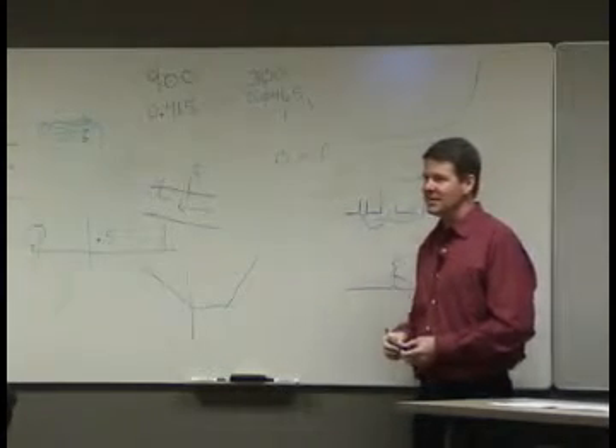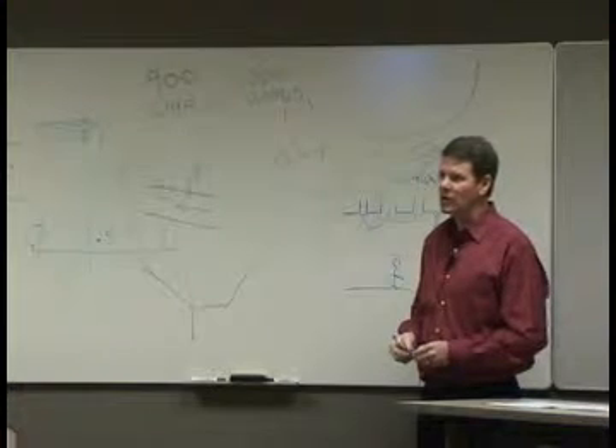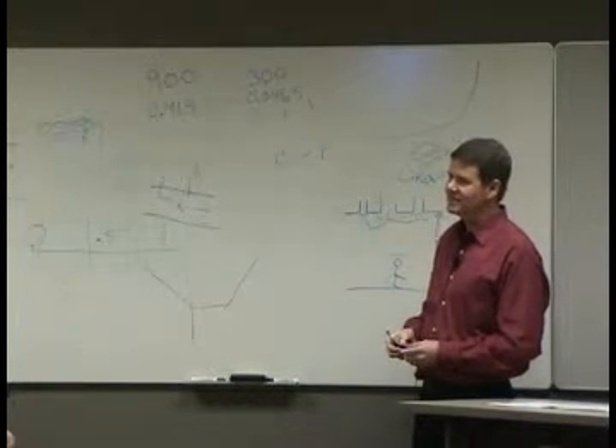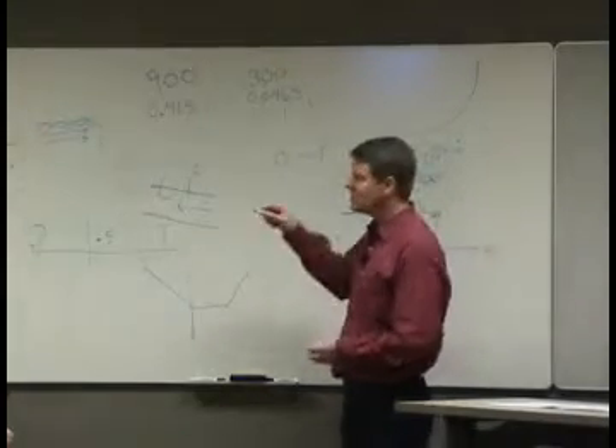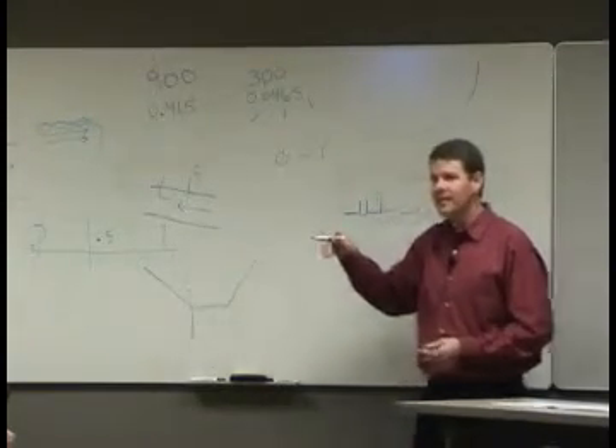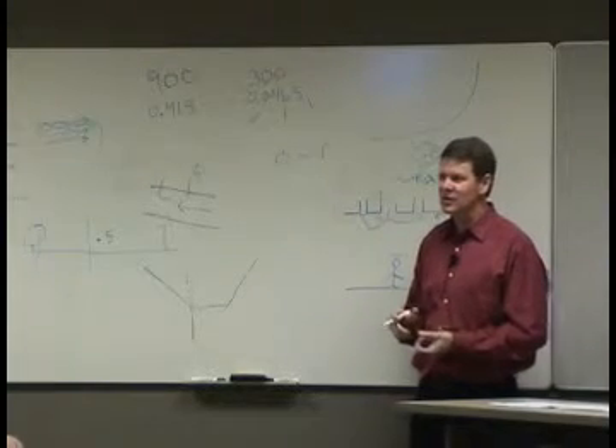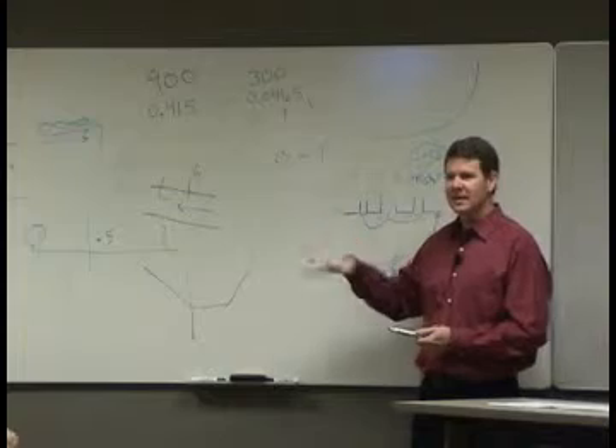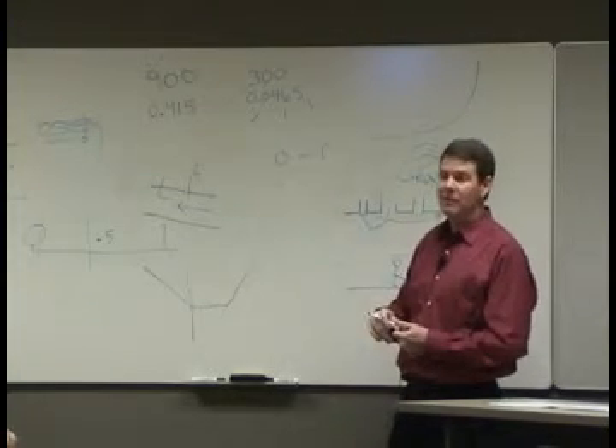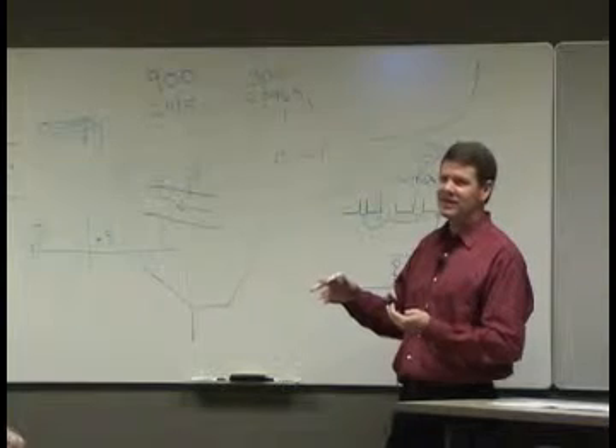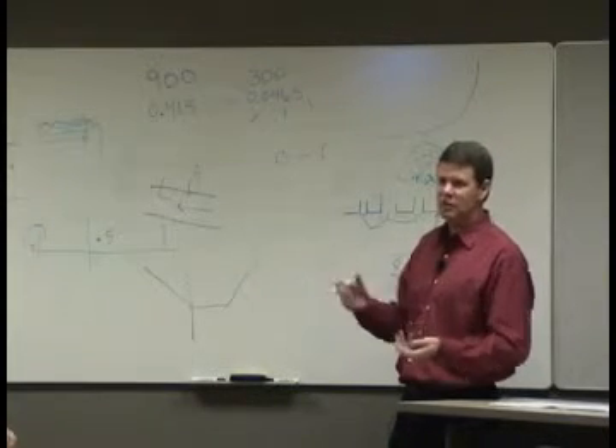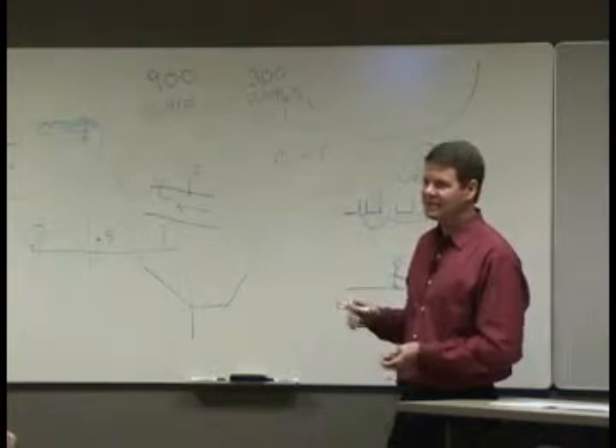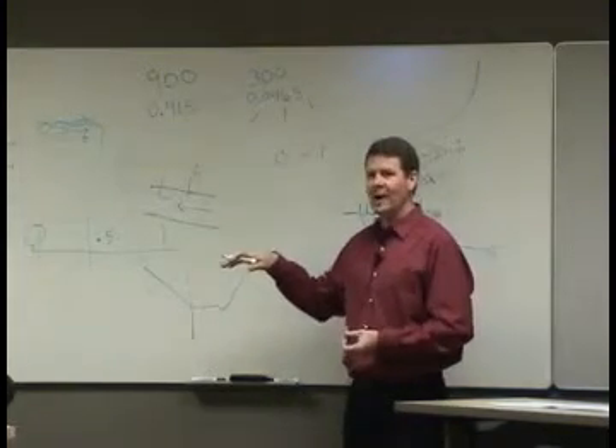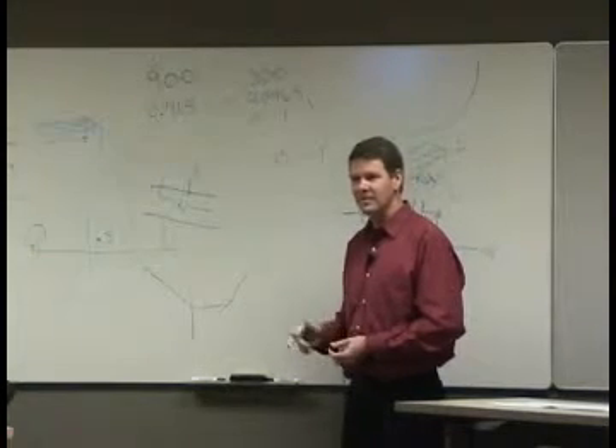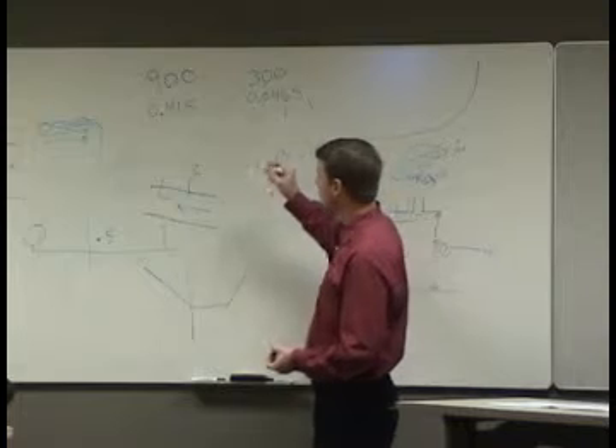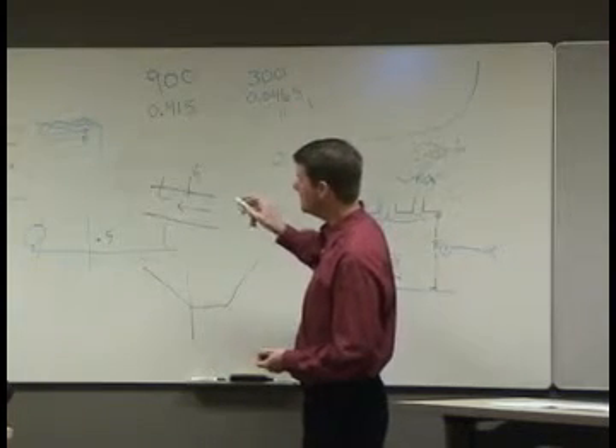You know, in my experience, it'll read below 0.1, but you get much below there and it kind of trails off pretty fast. Some of those sensors will get down to a velocity pressure of like, I want to say it's 0.017, and that's like the minimum they'll read. So if you have a big box, that may calculate out to be 500 CFM on a 2000 CFM box, it won't ever drop below that level, even with the damper completely closed, because of the resolution, you can't get down there.